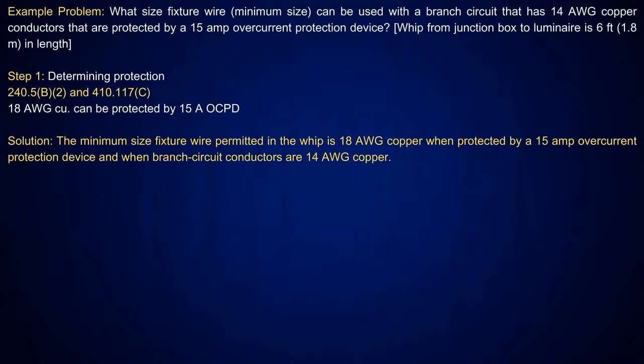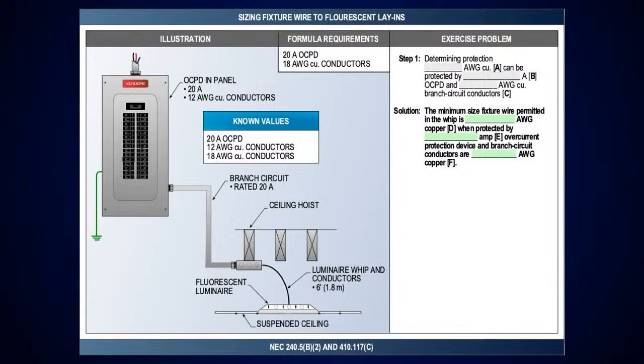Sure, I understand the terminology. But when you look at this, you've got 240.5(B)(2) to determine the protection, and it's not in 240.21, because they're telling you here that number 18 can be protected by a 15 amp overcurrent device. They have kept it separate for that reason, because some people may have called it a tap before. The reason they rewrote Article 240 is to get away from that. So when people say tap, I understand the terminology, just like we used to say just tap the secondary of a transformer. They had to rewrite that so it wouldn't happen, because people would size it differently.